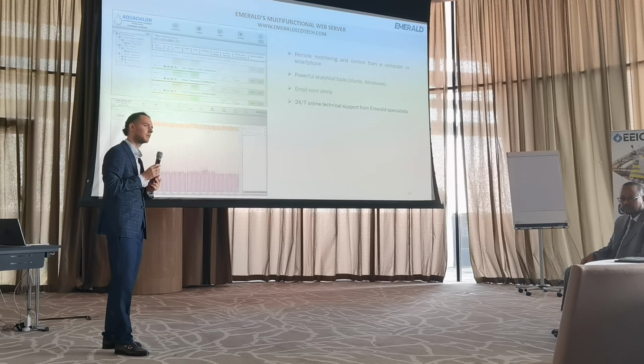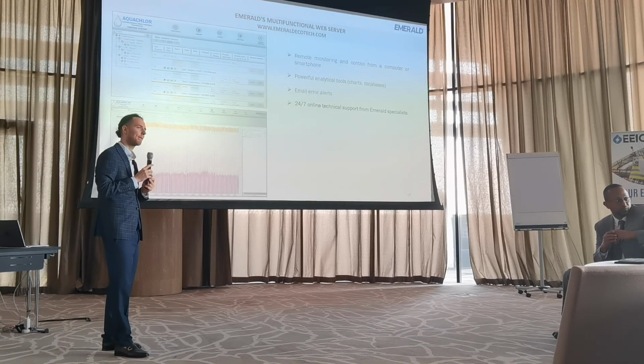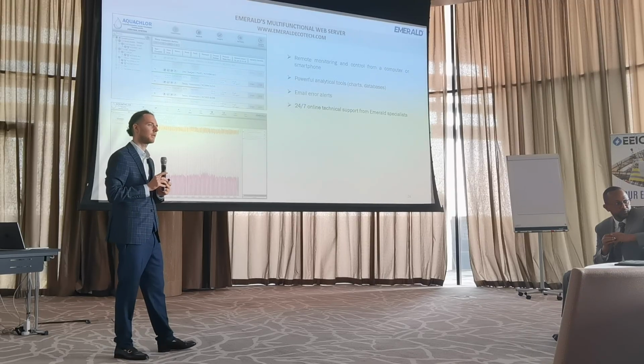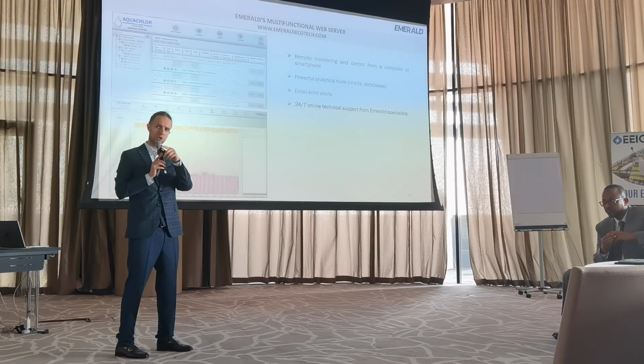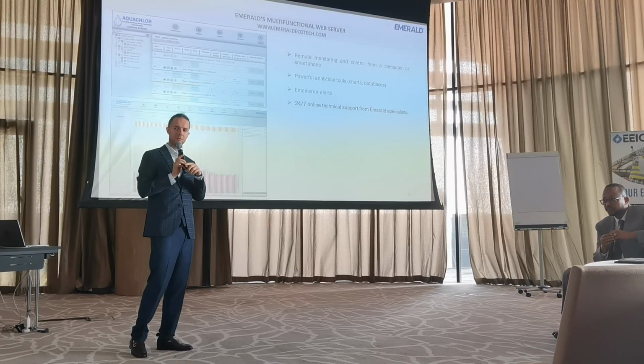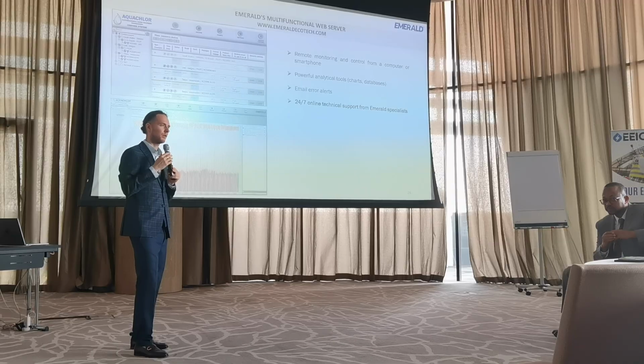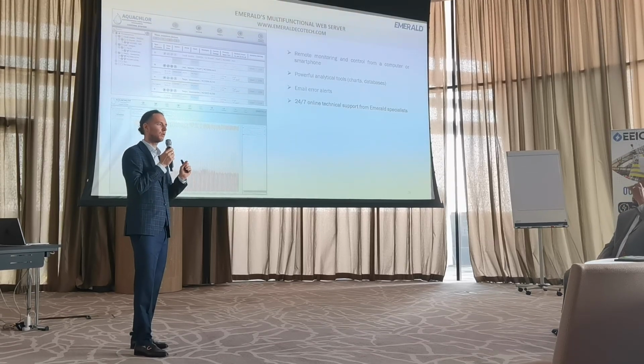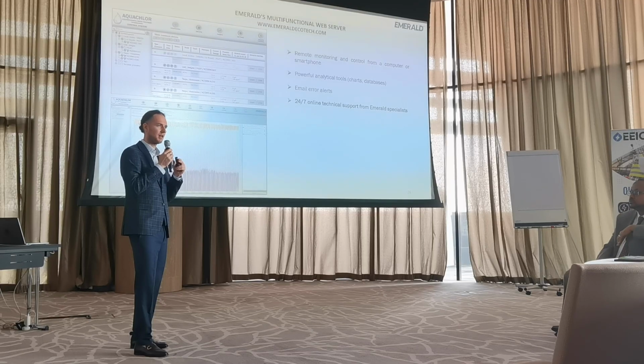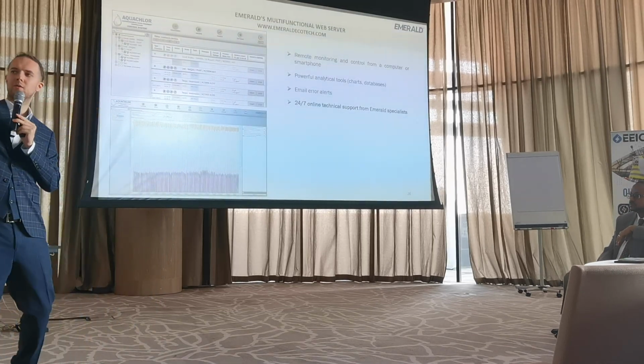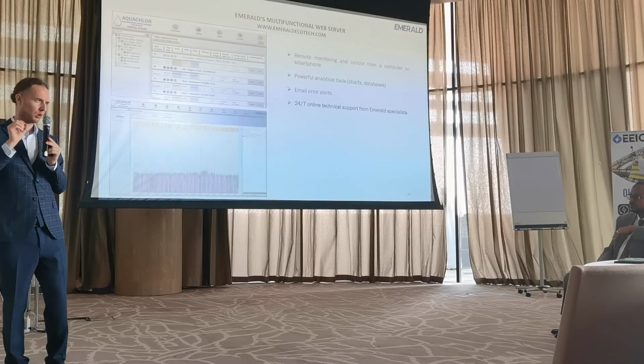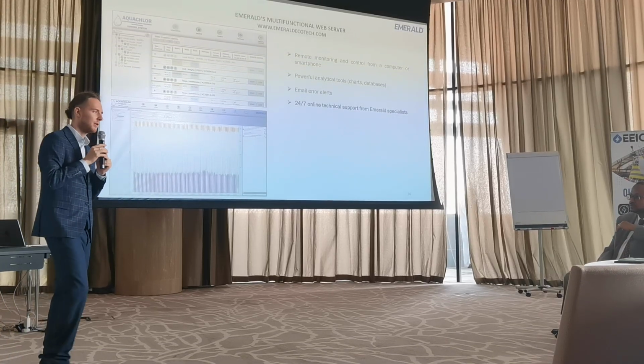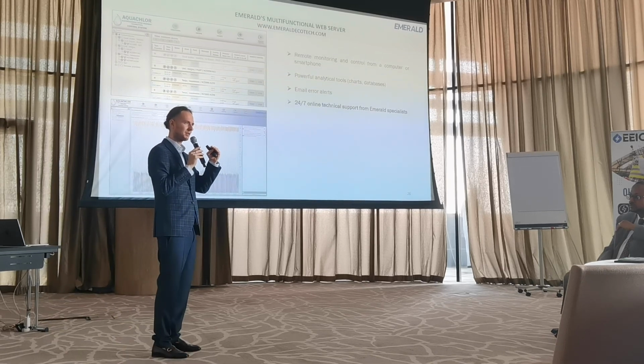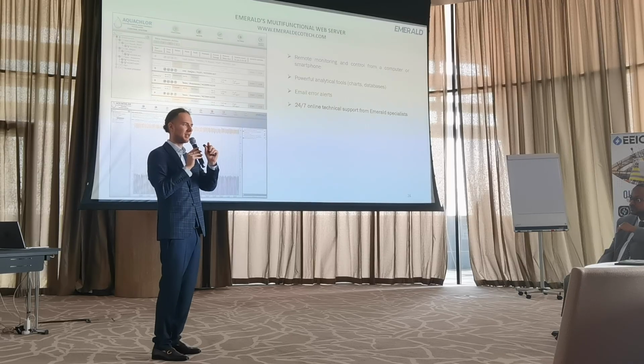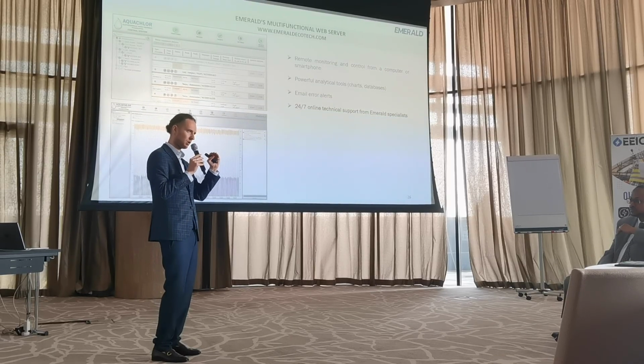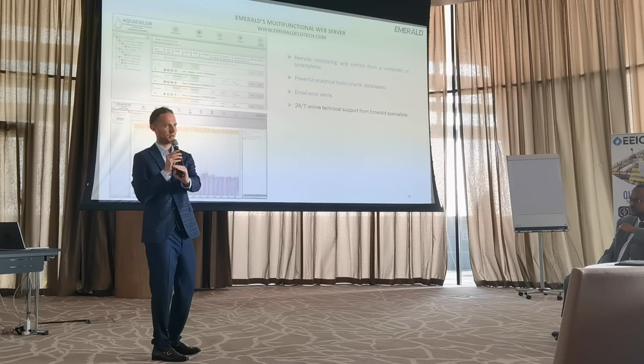So depending on the capacity of the flow rate, the production of the machine can be modulated? Yes. We will show during live operation. The very beautiful thing here is that production of chlorine, of active chlorine, of oxidants, fully depends on the current level. We have an AC/DC power supply here, which puts usually 5 volts on the cells. So if you increase the voltage, your current on the cell will increase, and production of chlorine will increase. If you reduce the voltage, current will decrease, production of chlorine will decrease.